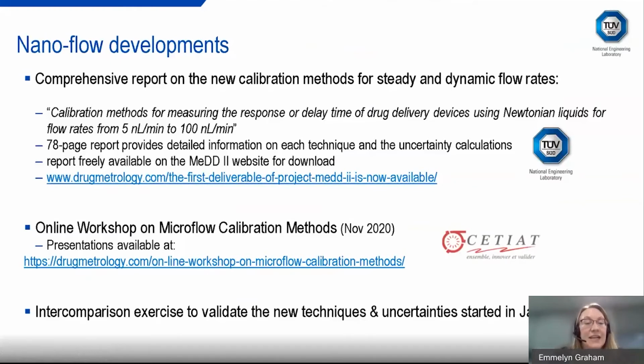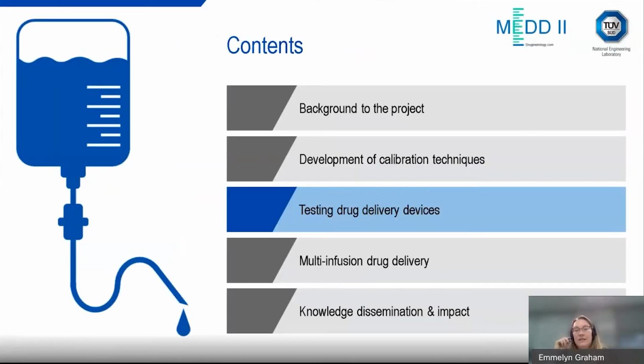The next stage is we have just begun doing an intercomparison exercise, and this is where we have two thermal flow meters and a syringe pump, which is being circulated around all the laboratories in Europe, so we can establish and compare the results from each facility. Because what you want to ensure, if you test a drug delivery device in one organisation, you're going to get the same results and values as if you test it in another organisation, and there's no bias in the results. So we're going to move on to testing the drug delivery devices.